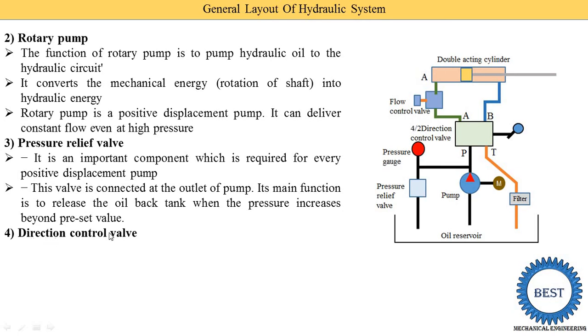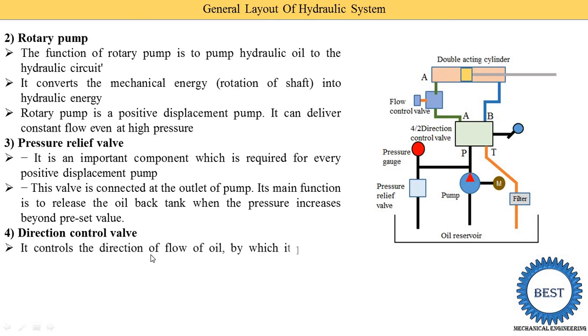The next component is the direction control valve. From its name, you can understand that it changes the direction of oil or guides the oil in the proper direction. It is not necessary that the oil from the pump is supplied to only one system. Since we use a double acting cylinder, we need to supply oil in two directions — either through pipe A or through pipe B. The direction control valve decides this, sometimes supplying oil through pipe A and sometimes through pipe B. It controls the direction of flow of oil, by which it performs extension and retraction of the actuators.